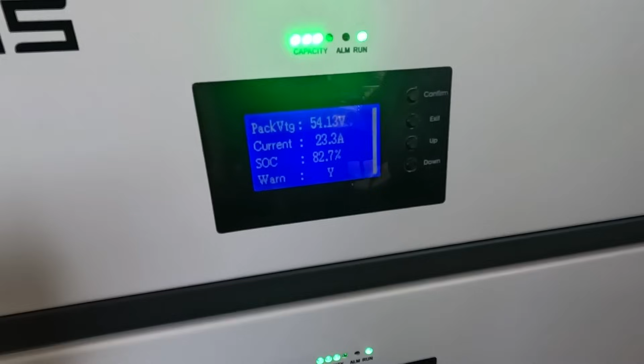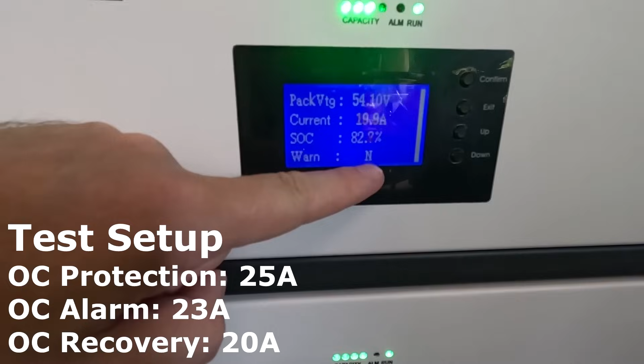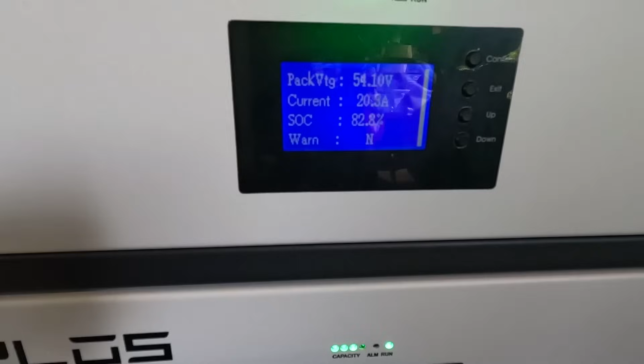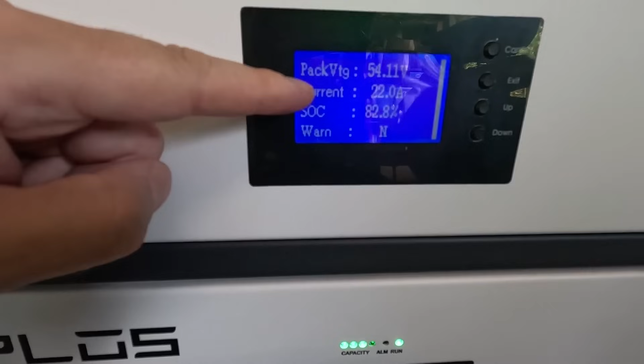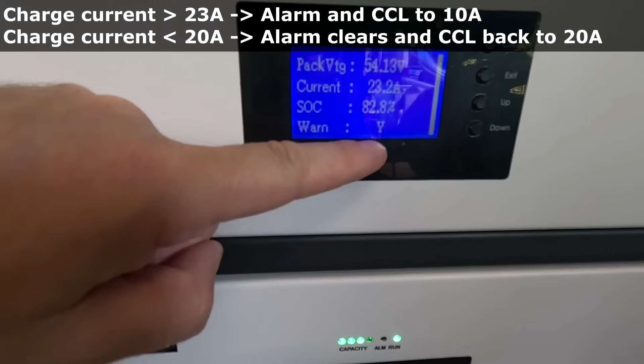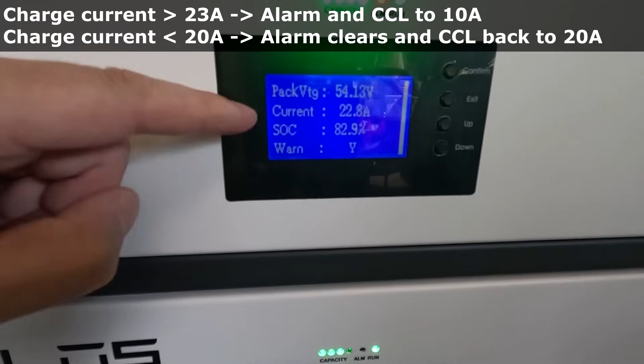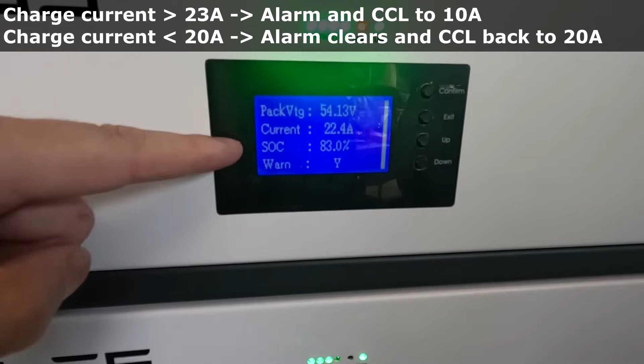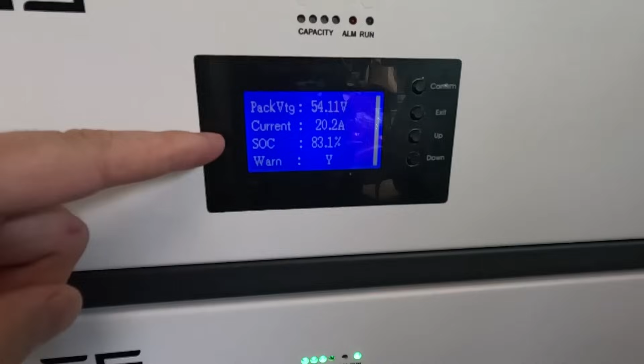So we are going into an alarm with the top battery here, battery number 1, our master. See, we are going over 23 amps, and this triggers the alarm as per our settings. You can see the warning here, it's a Y. Now it is under 20, it recovers, and goes back to reporting a CCL of 20 amps. But then the current goes up to 23 again, the warning comes back, the LED comes on, and it reports only 10 amps to the solar charge controllers. So this mechanism actually works, that is totally fine - this is exactly as we programmed it. 25 is our maximum, then it would shut off, but a warning reduces only the CCL to 10 amps. This is what Seplos does. It's not a bad thing, but it's not really necessary either. But as you can see here how it works, right?